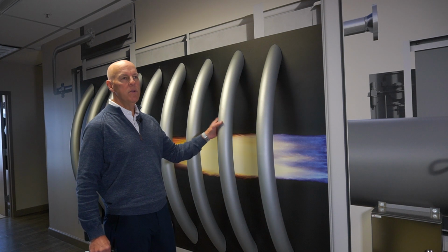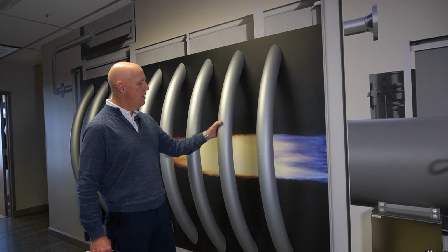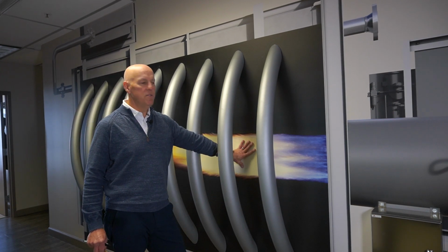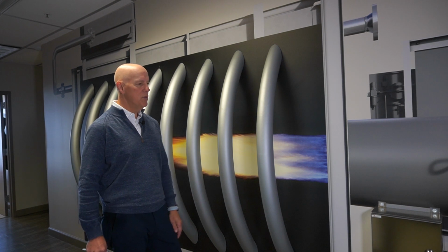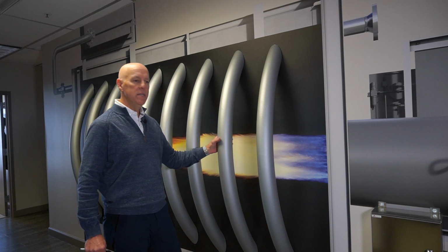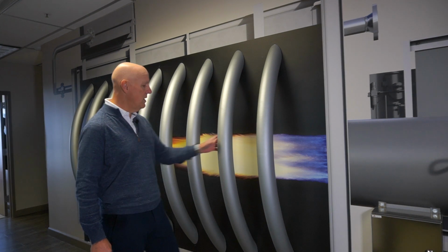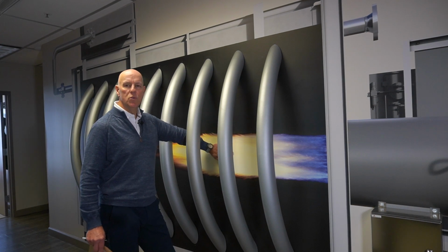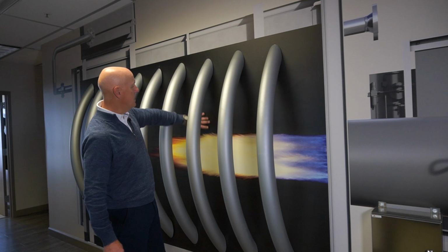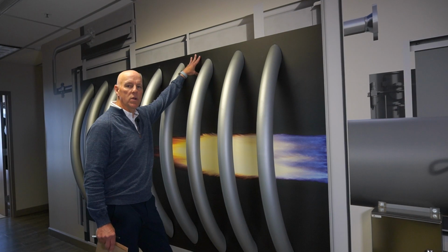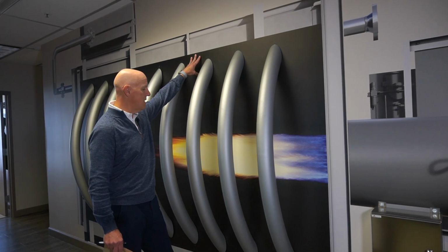And what we're looking at here, these are the process coils. This is the pipe that the fluid flows through that we're trying to heat. Obviously behind this is the flame, and it's created by natural gas and combustion air and a burner. So the heat from this flame is heating this coil, and then the pipe itself is heating the fluid inside. The temperatures you see in a typical heater in a flame might be 2200 degrees. Outside of the flame, it gets colder, hence you can see the black, and it may be in the range of 1200 to 1500 degrees outside of the flame.